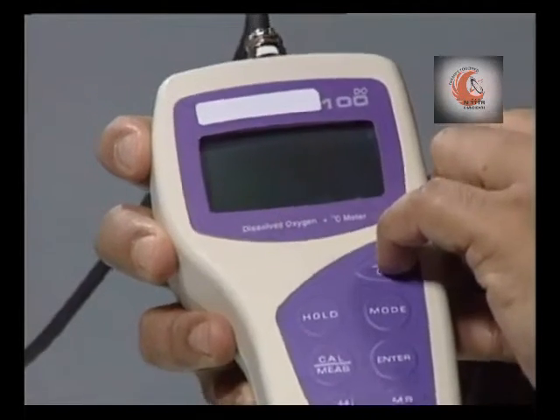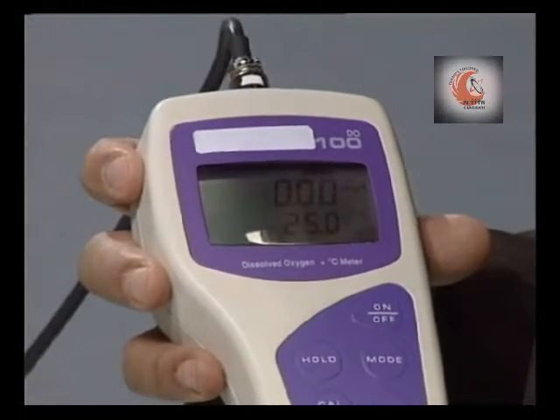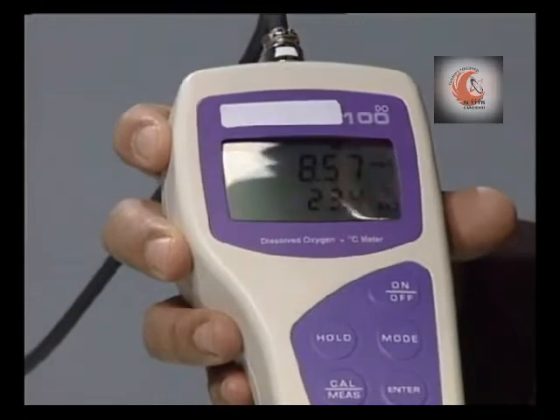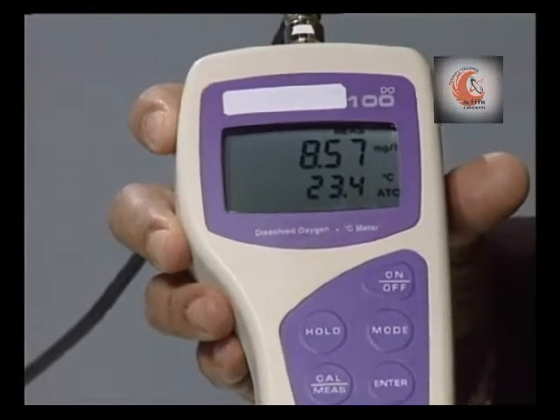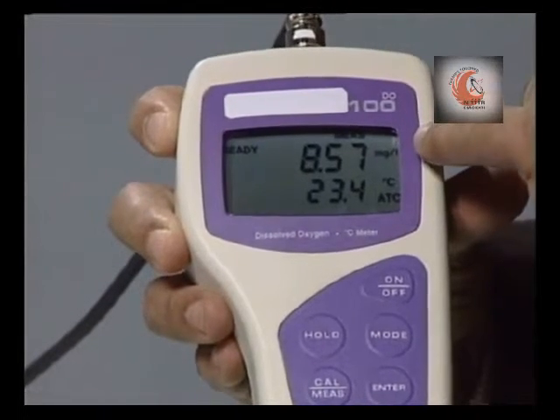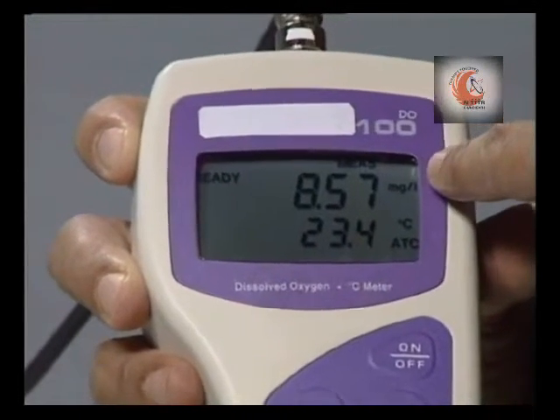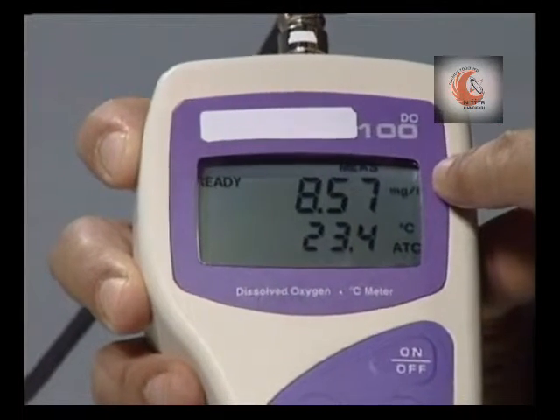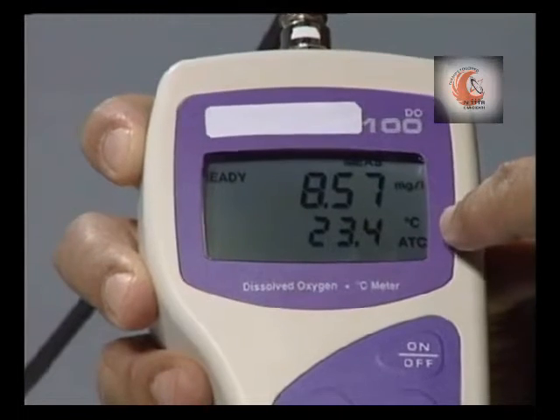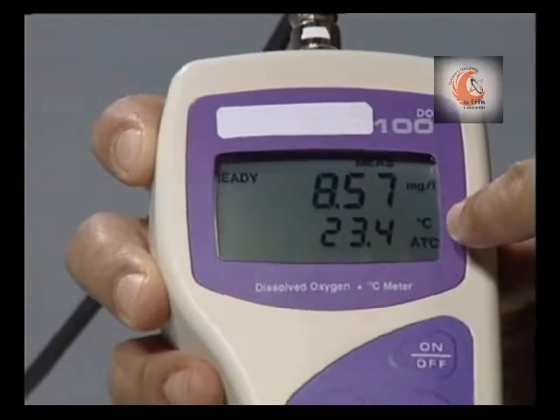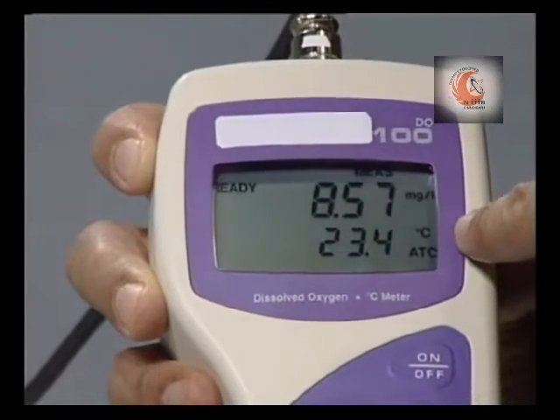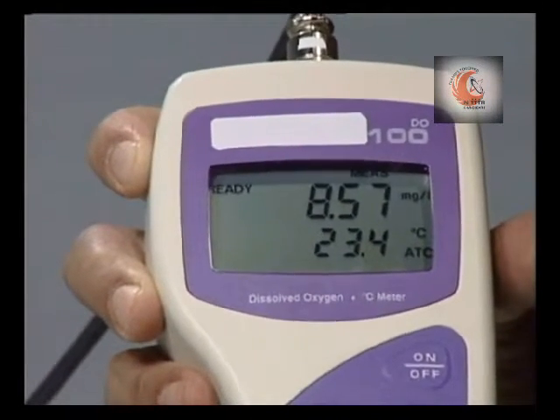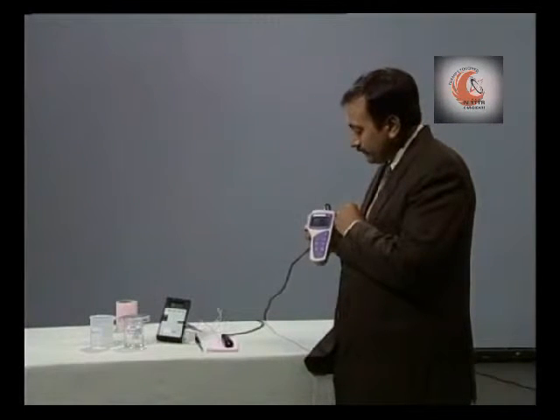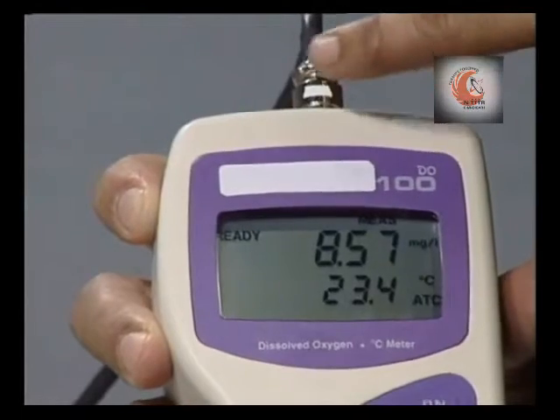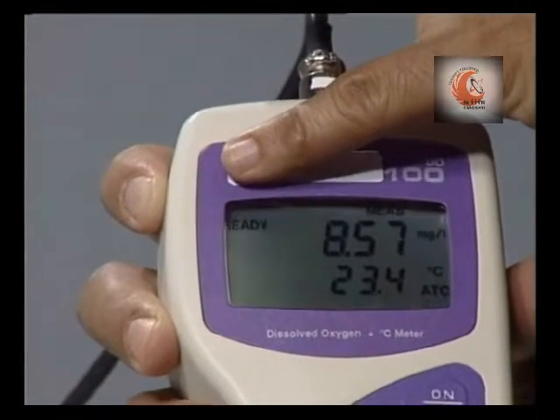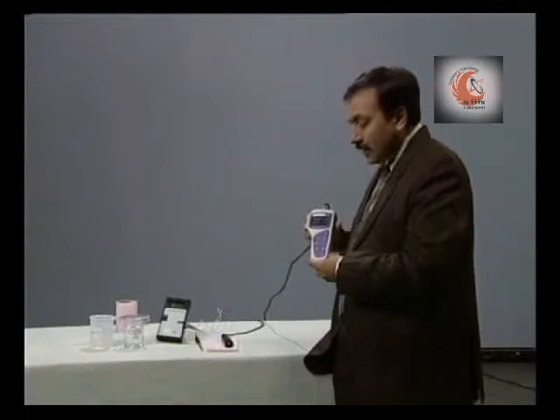Now, switch on the instrument. So, we can see that a display is made here. On the right side we see mg per liter. This shows that the instrument is in DO mode, and the bottom display shows the temperature, and the ATC annunciator indicates that automatic temperature correction will be carried out by the instrument. When the instrument is ready, the corresponding display will be made on the left side.